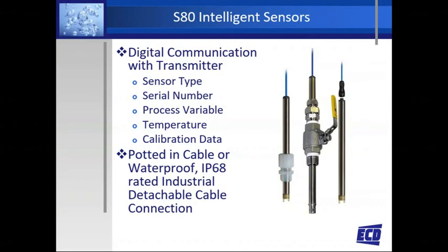Also, since it's uploading the calibration data, you can calibrate the sensor on a bench in your lab and then take it out and just attach it to the transmitter, and it'll upload the data and be calibrated. You don't have to perform the calibration in the field. The sensor is available with a potted-in style cable or an IP68 rated detachable connector. We'll show the actual connector a little bit later. The connector comes in handy when you're going to calibrate on a bench and then take it out and attach it to the transmitter.